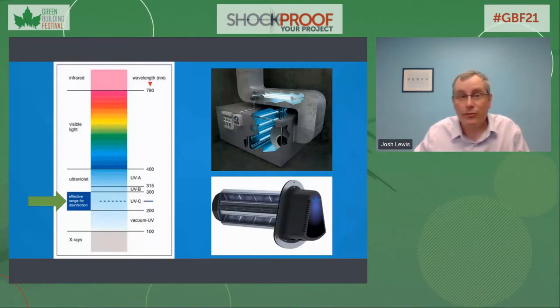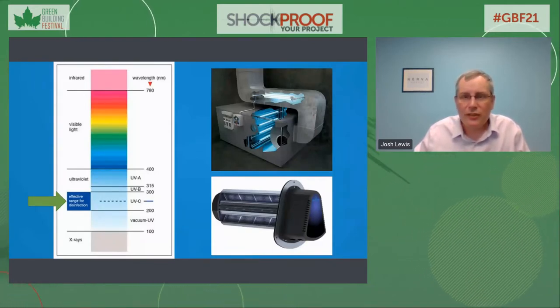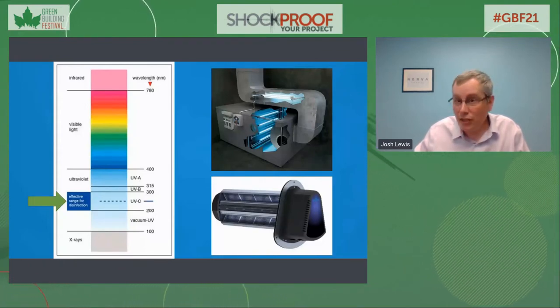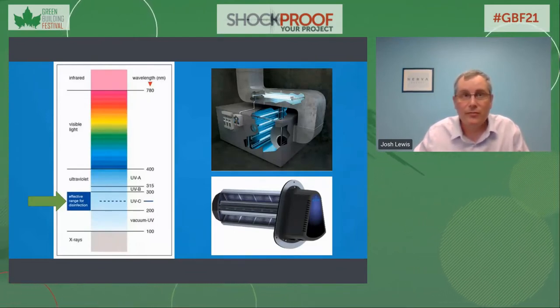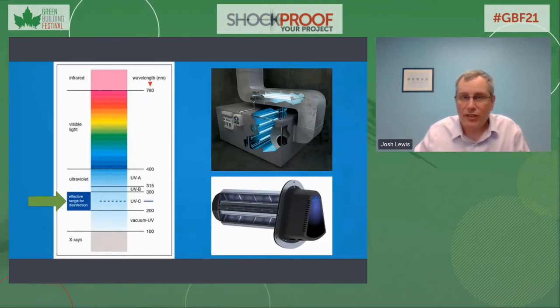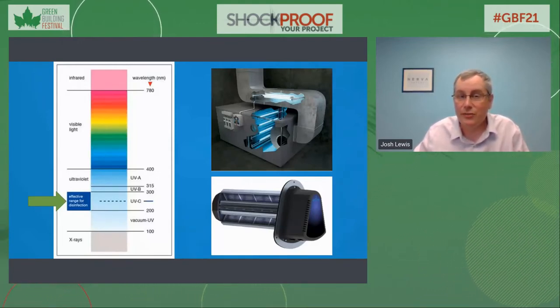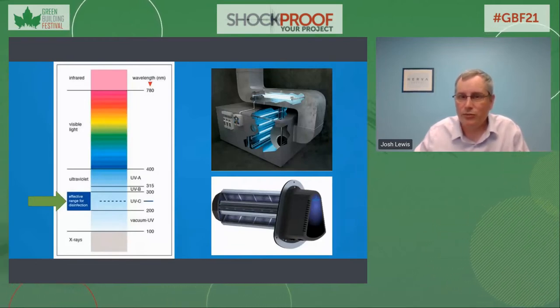UV light is electromagnetic radiation with a wavelength shorter than that of visible light, but longer than X-rays. It covers the wavelength from about 100 to 400 nanometers. For disinfection, AKA purification, the process typically uses wavelengths in the UVC range from 240 to 280 nanometers. By properly installing UV lights into the ductwork, the air passing by them can have any biologics within it inactivated due to exposure to the rays. For safety, it is critical that the lights are completely contained, as direct exposure to their output can have harmful impacts to anything living, including but not limited to the injury of sensitive cells contained within the eyes, creating the potential for blindness, which we certainly want to avoid.